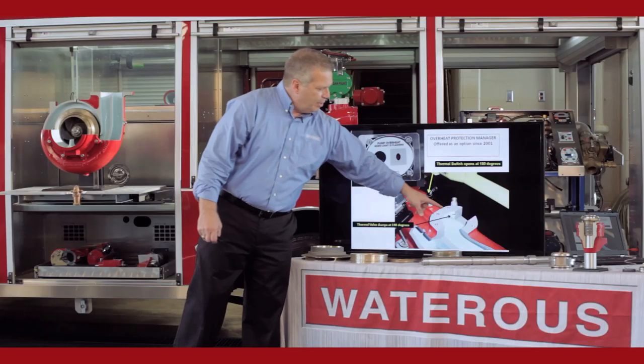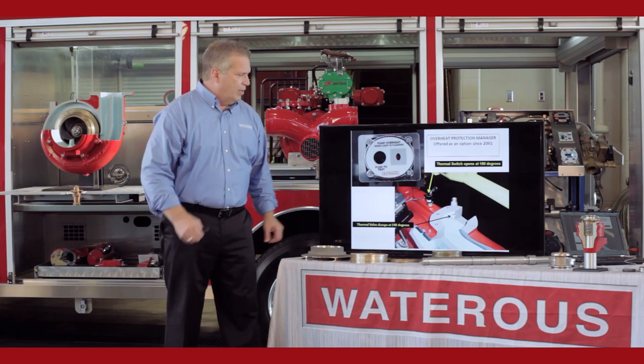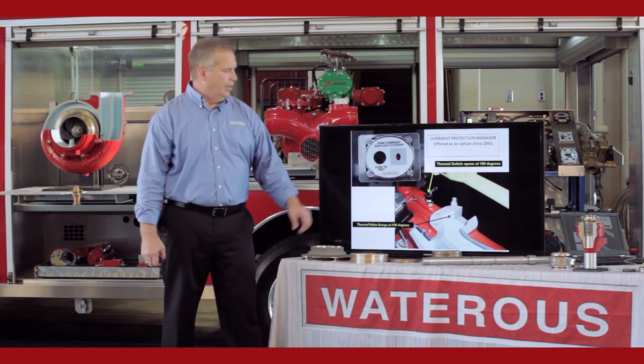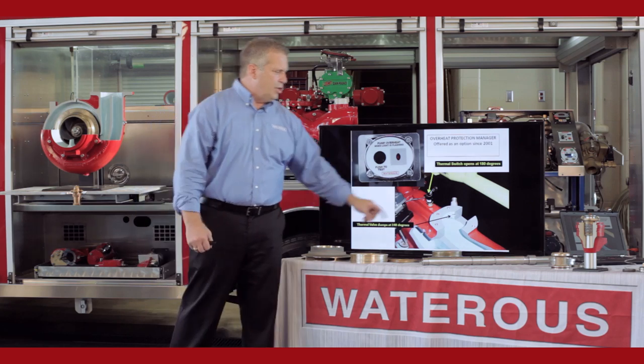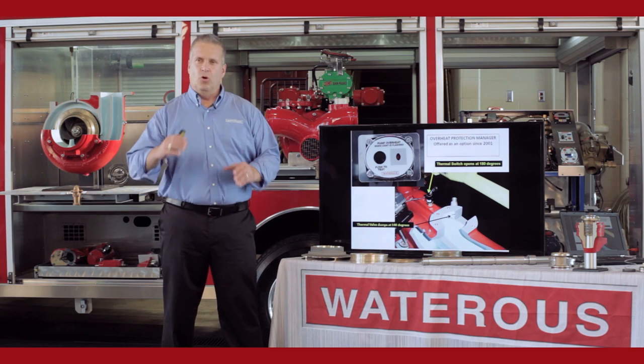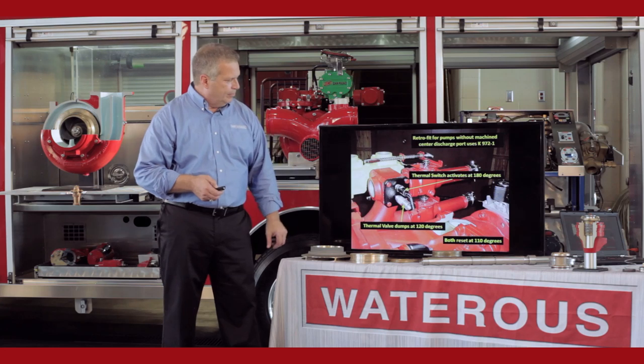Some of the Waterous Company offers is an overheat protection manager. You have two parts to the system: a dump valve coming off the center discharge of the midship style pump — or plumbed into a different port on an end suction or different type of pump — that dumps at 120 degrees and resets at 130. You have another part of the system with a sensor that goes off at 180 degrees, turning on a flashing light on your pump panel — an audible alarm is also available. The system is there to warn you that something is going on with the pump so you can flow water to cool it. It can be retrofitted to older pumps by adding a flange out to a discharge fitting to sense that temperature rise.